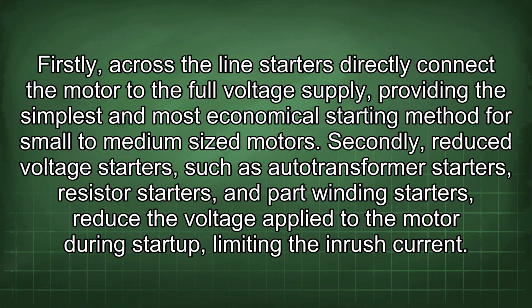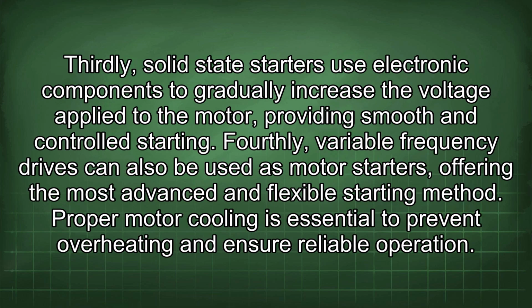Secondly, reduced voltage starters, such as auto-transformer starters, resistor starters, and part winding starters, reduce the voltage applied to the motor during startup, limiting the inrush current. Thirdly, solid-state starters use electronic components to gradually increase the voltage applied to the motor, providing smooth and controlled starting. Fourthly, variable frequency drives can also be used as motor starters, offering the most advanced and flexible starting method.